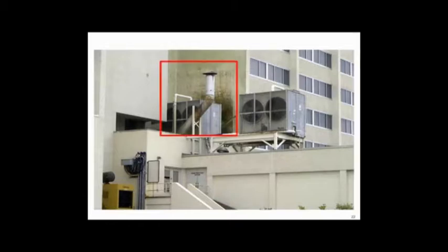But what I'm saying to you is, you see the tower between the two walls, that's the airflow. Now, that wall is green. You don't want to get near that stuff. That's going to be bad. Do you begin to understand how the warm, moist air would just wrap around and around and around? There's no way you're going to get certified tonnage out of this thing. There's no way I could get 100 tons. The best they could do was about 50.